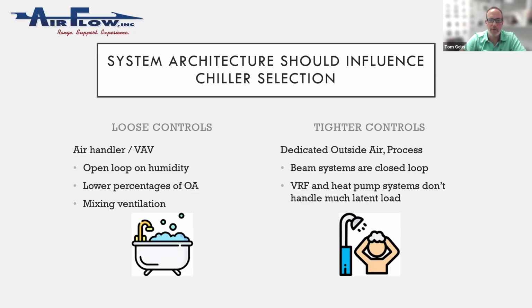necessary. Whereas, if you're going to do a chilled beam system, if your DOAS system is going to be tightly controlled, if your heat pump or VRF systems don't handle latent load, then it may be time to switch, like moving from a scroll chiller to a screw chiller. It just goes to how tight do I need to be? And I think a lot of times people just pick chillers based on what the budget is, but it may be just something to consider that we use tighter controls depending on the system and looser controls depending on the system. And I'm sure designers take that into account, but sometimes like I need a chiller, and we've got to think about those little details about the controllability of it. So that's all I had on that particular subject.